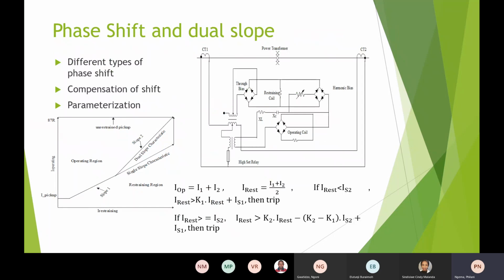Then on the phase shift and the dual slope, what I am going to be focusing on here is that transformers have different phase shifts. Those phase shifts tend to contribute a lot to unnecessary tripping of the relays, because they are not compensated very well. It is one of the studies that I am going to look at: how to compensate the phase shifting, as some of the relays even require interposing CTs. I am going to look broadly at different types of relays, and also include the tap changing system.